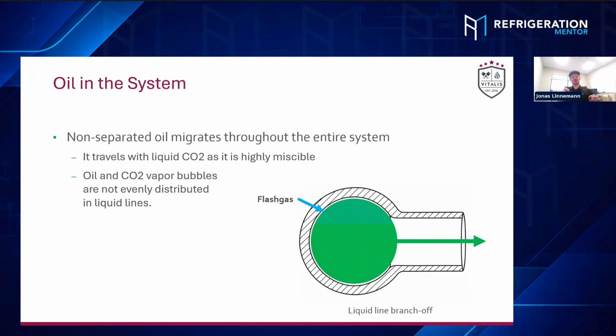CO₂ is different because we have this 2-stage expansion, and once the pressure dropped into the liquid receiver, you have lower temperatures of the liquid. So we do have 2-3 degrees C of liquid temperature. There are internal heat exchangers for subcooling, but still the environment is warmer. So the heat travels into the liquid line and basically boils off a certain small amount of liquid CO₂. And any pressure loss would cause some flashing of the liquid. So that's the main difference between CO₂ systems and conventional condensing systems with HFC. And that's why you have to expect to have some amount of flash gas in the liquid lines.